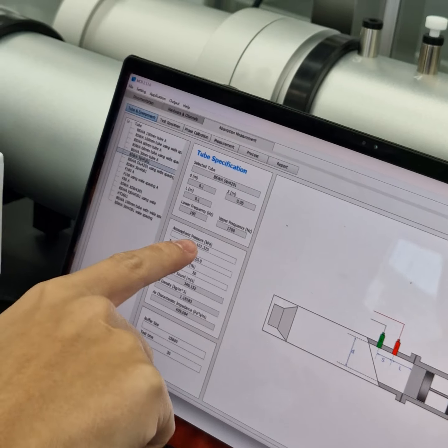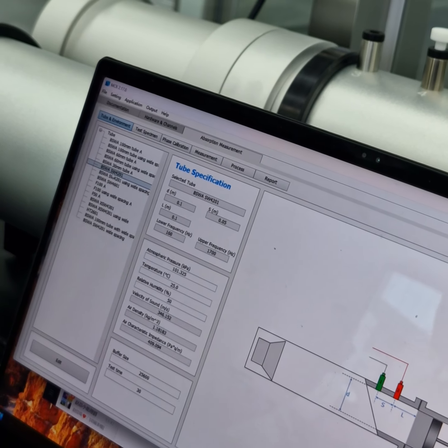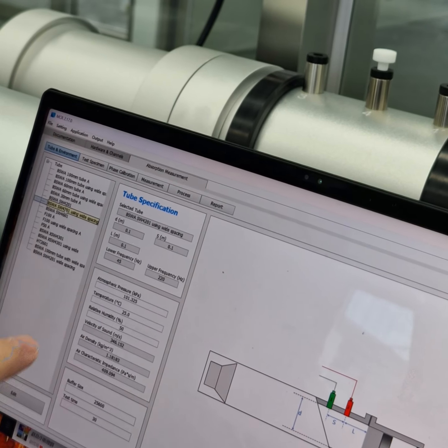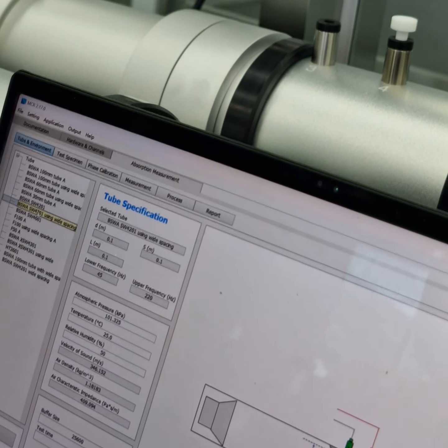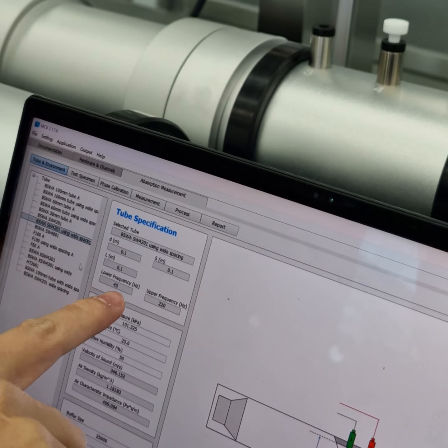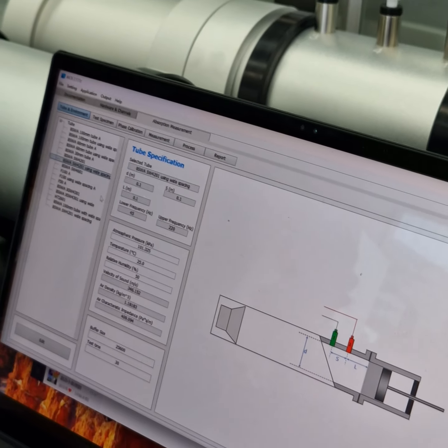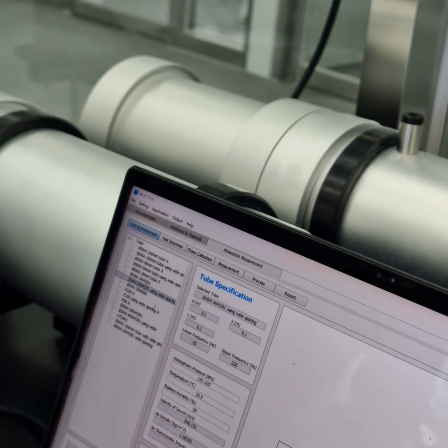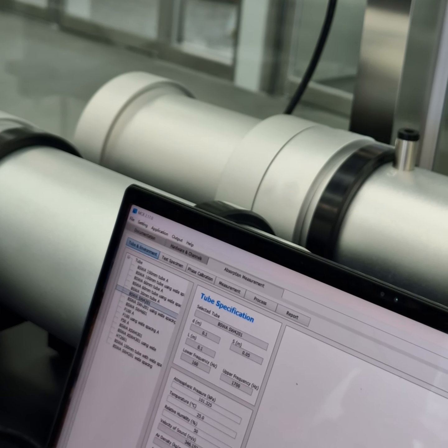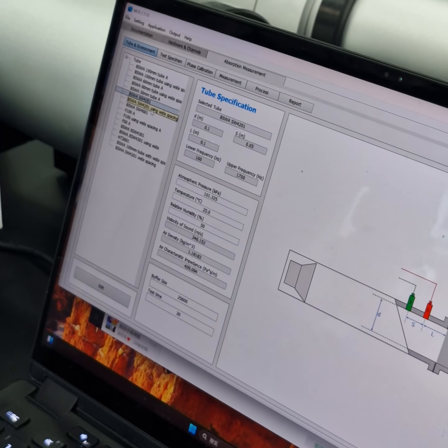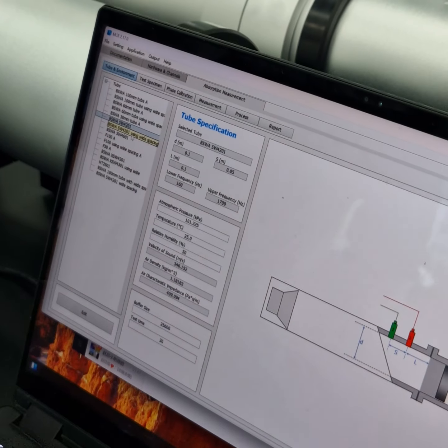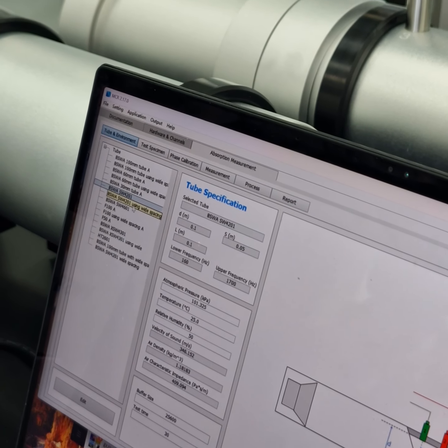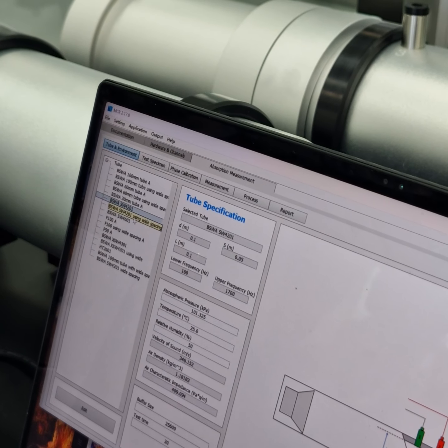The upper frequency is going to be 1700 hertz, but if you're using the wide spacing, it's going to be 220, and the low frequency is lower. Sometimes you need to test low frequency, then you will use the wide spacing. But usually this is 160, which is sometimes enough. So it depends on your needs and your requirements.